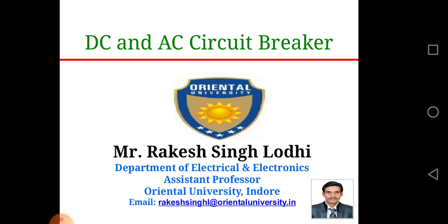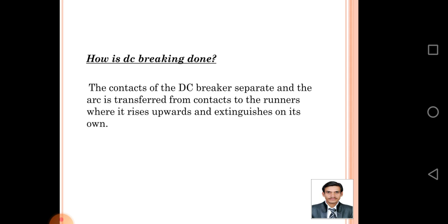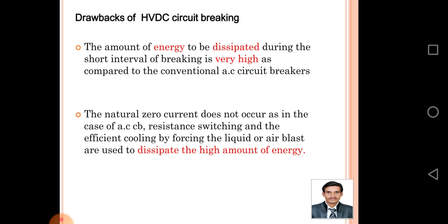How is DC breaking done? The contacts of the DC breaker separate and the arc is transferred from contacts to the runners, where it rises upwards and extinguishes on its own. Drawbacks of HVDC circuit breaking: the amount of energy to be dissipated during the short interval of breaking is very high as compared to conventional AC circuit breakers.